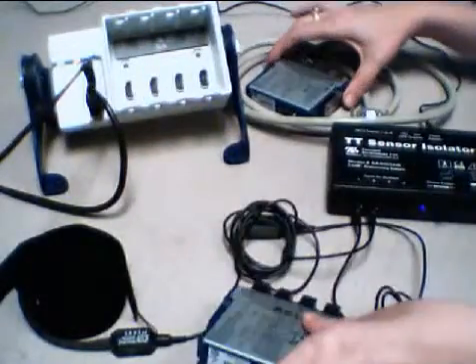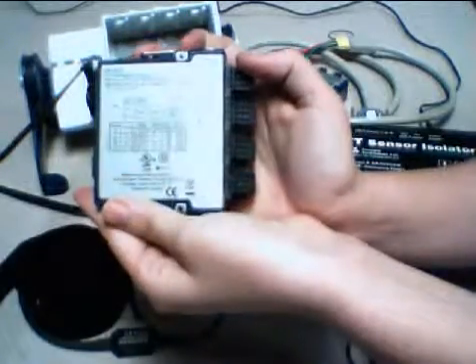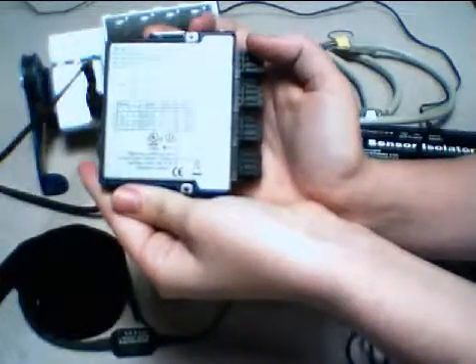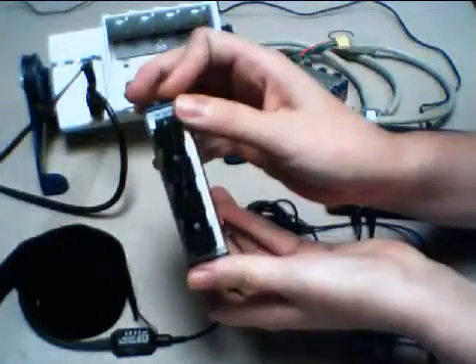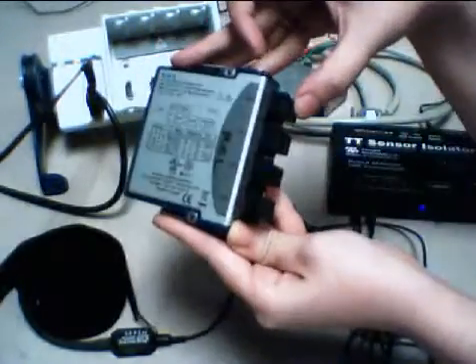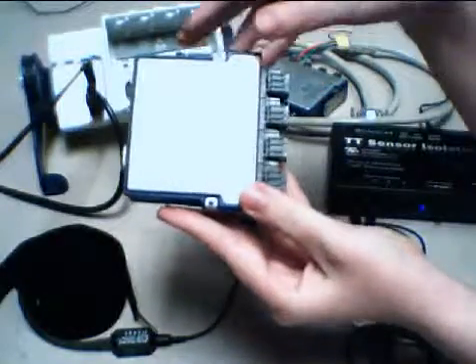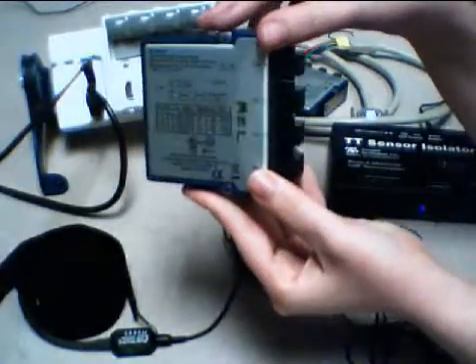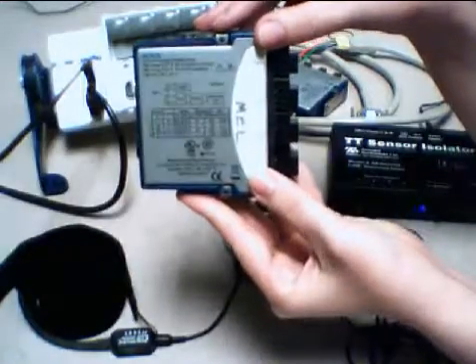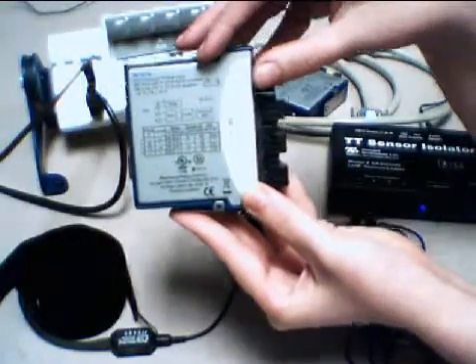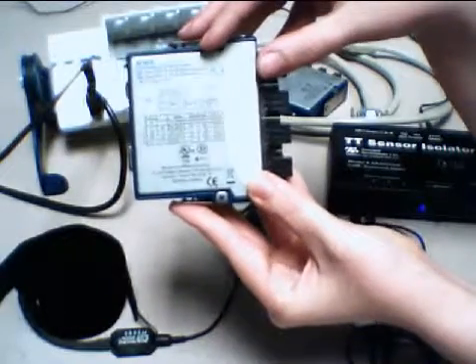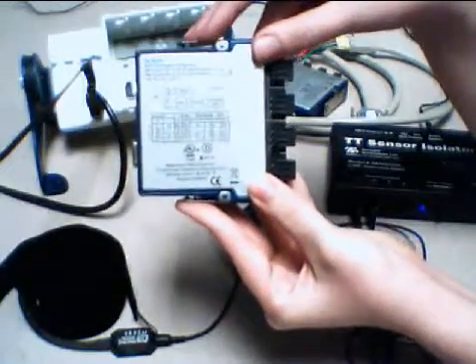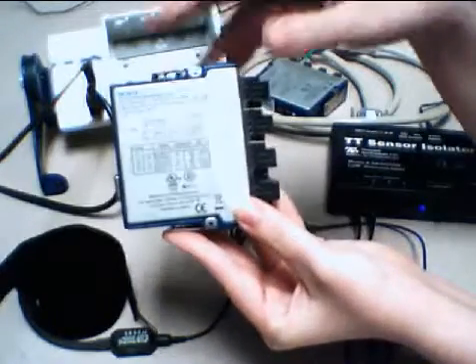Now, this module right here is the 9219 universal input module and basically it has four channels, each with a six pin screw terminal. The reason why it's called a universal input module is because of its versatility. It's capable of measuring voltage, current, resistance, strain gauges, temperature, any number of signals that might be of interest in a biophysical application.